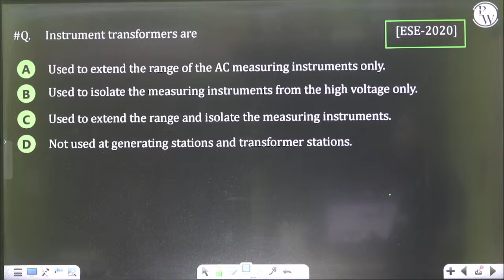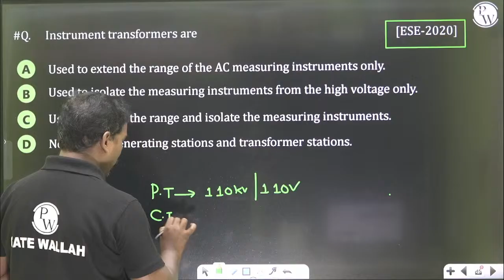For example, a potential transformer converts 110 kilovolts to 110 volts. A current transformer converts 100 amperes to 5 amperes.